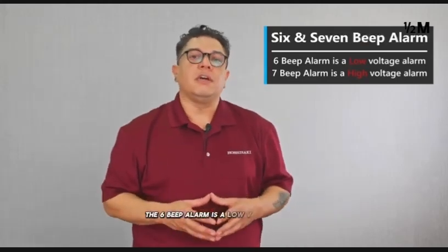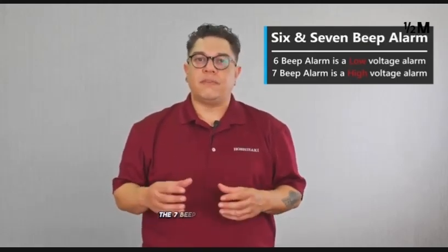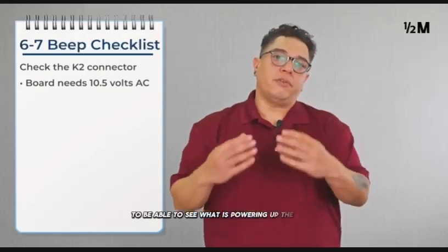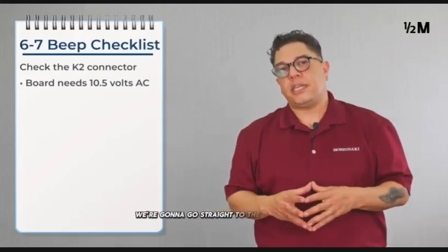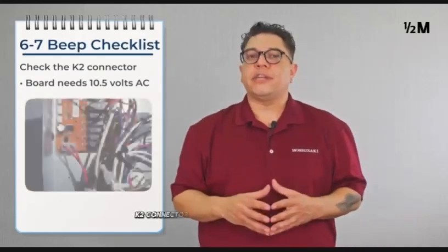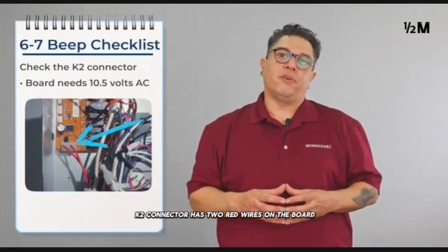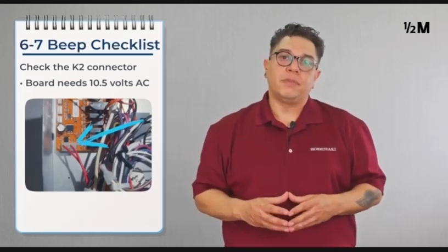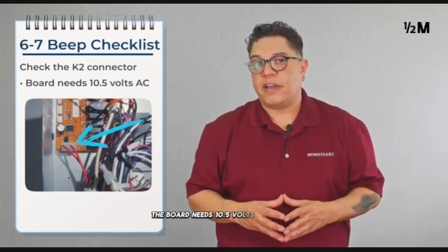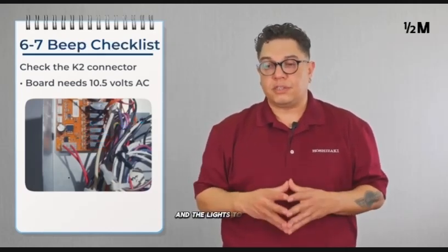The next alarm that we're going to look at is the 6 and 7 beep alarm. The 6 beep alarm is a low voltage alarm. The 7 beep is a high voltage alarm. To be able to see what is powering up the board, we're going to go straight to the K2 connector. K2 connector has 2 red wires on the board, and that's how the board gets power. The board needs 10.5 volts to turn on and the lights to turn on.